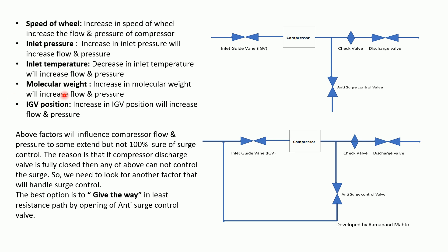We cannot use any of those factors for surge control, because if the compressor discharge valve is fully closed, none of the above parameters can control the surge. If the discharge is closed, none of those factors will help. So we need to look for another factor that will prevent surge.